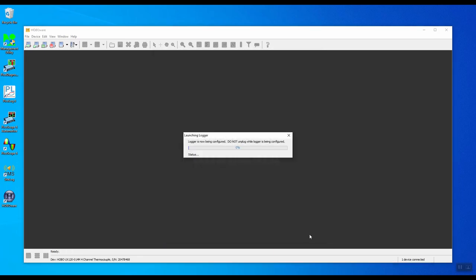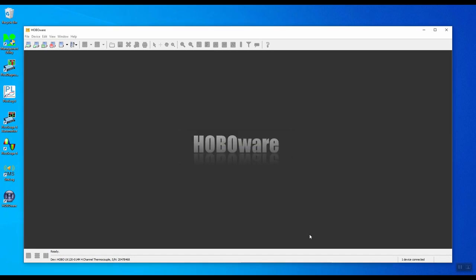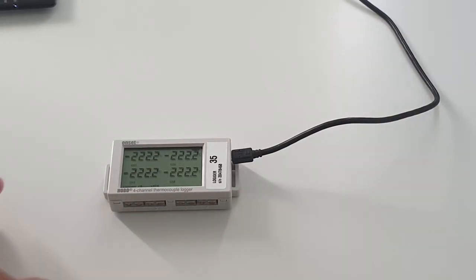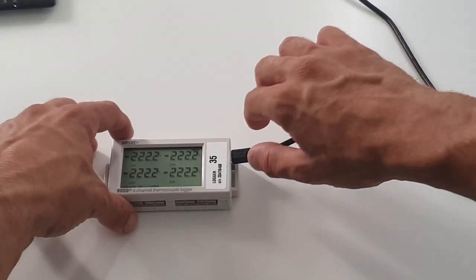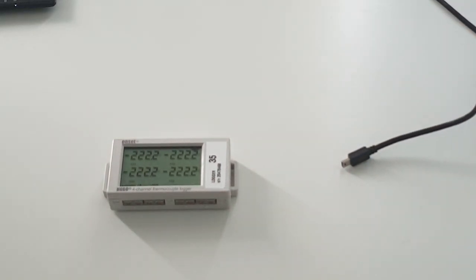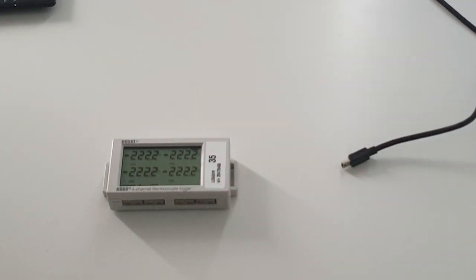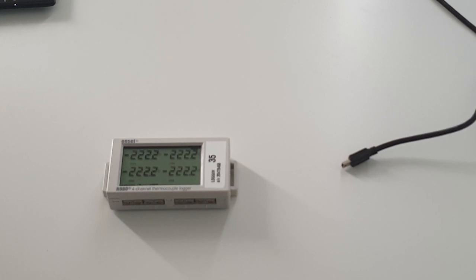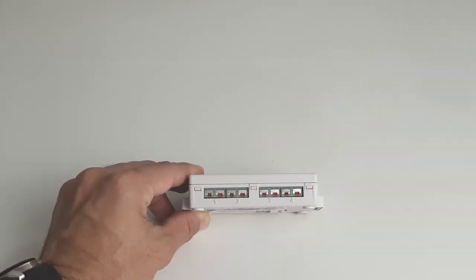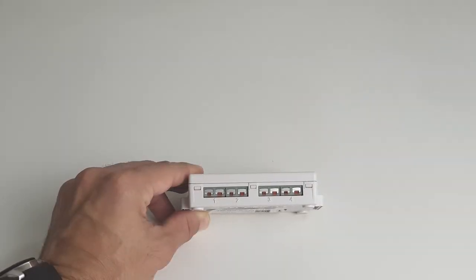Now it's sending the configuration information to the data logger, and now it's ready to start recording. You can close the software and unplug the data logger from the USB port. You'll notice that the readings are giving us minus 222. That's because nothing's connected to them and it's open circuit. Let's talk about the input connectors.